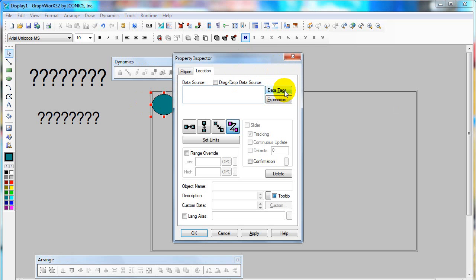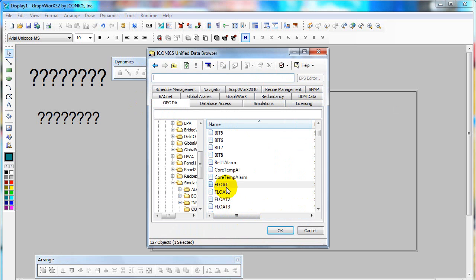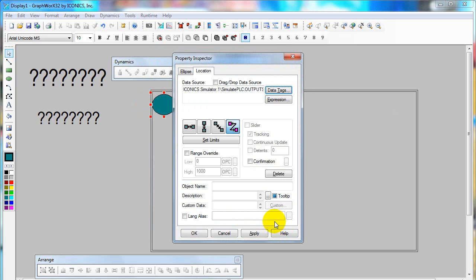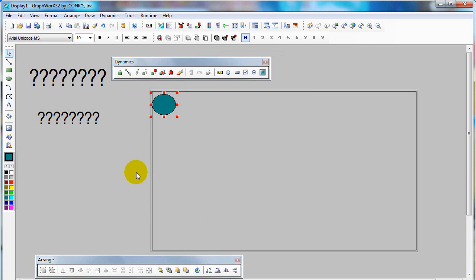And then click on data tags to choose the OPC tag. I use float. You need to specify the range override. In this example, I will use 0 to 1000 and then click OK.